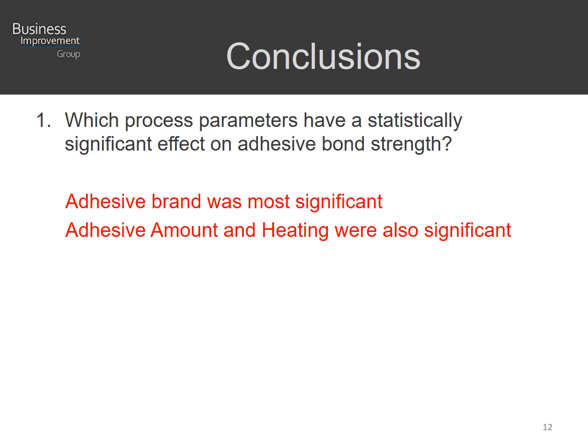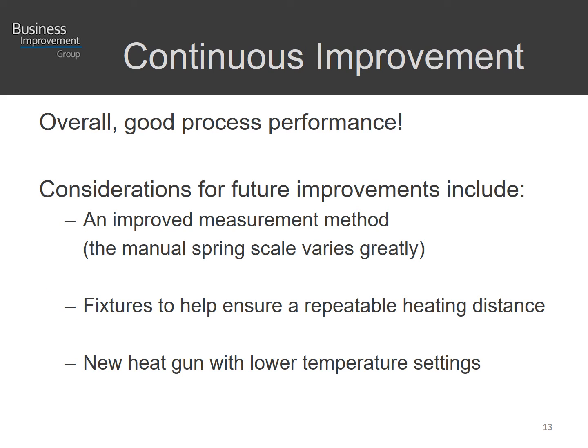Conclusions of this study: which process parameters had a statistically significant effect on adhesive bond strength? The adhesive brand was most significant. The adhesive amount and heating were also significant, and we were able to optimize those to get the strongest bond. The process capability with optimal bonding process settings demonstrated a PPK of 1.56. If the acceptance criteria for this application is 1.33, this would pass; if it were 1.66, it would not.